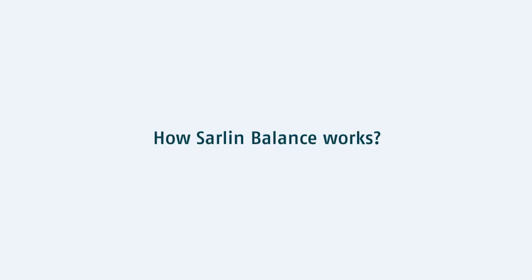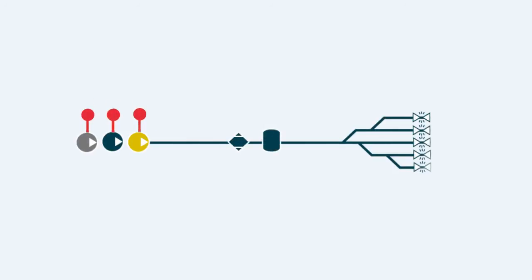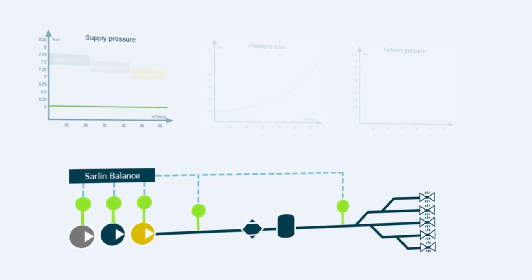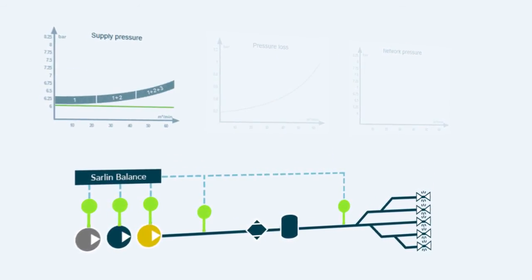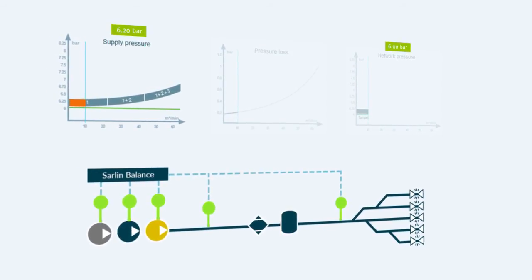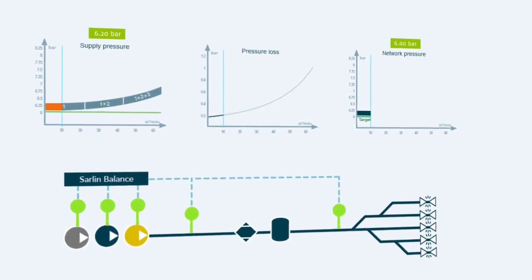How Sarlin Balance works? Sarlin Balance measures the pressure in the compressor station, and in at least one point in the compressed air network. This means that the compressors no longer operate according to fixed limit values, but Sarlin Balance controls them continuously so that an optimum pressure level always prevails in the point of usage.